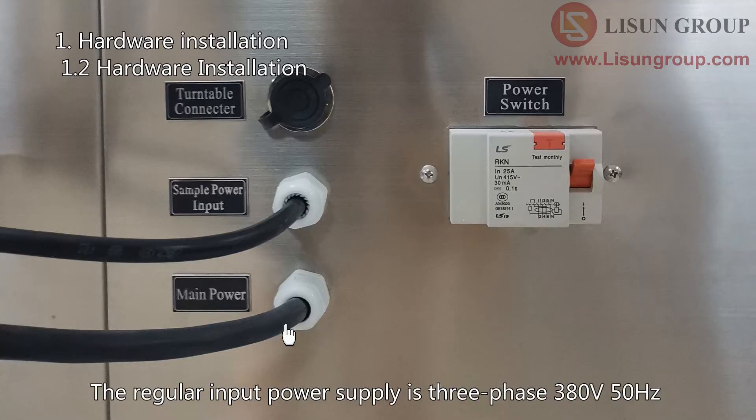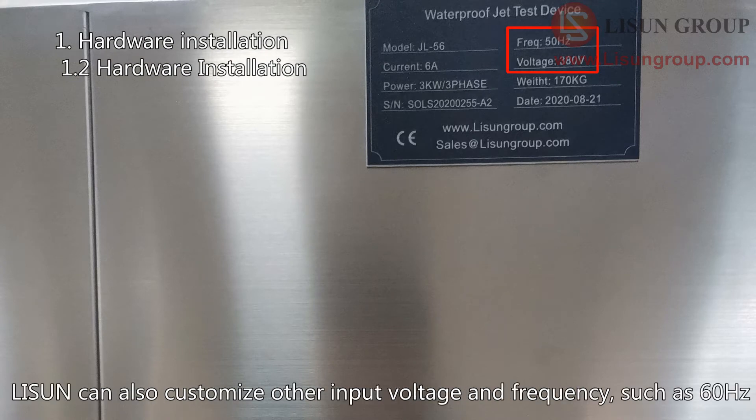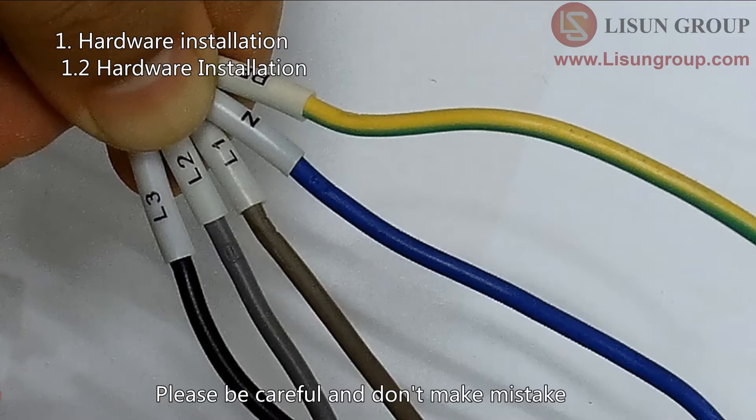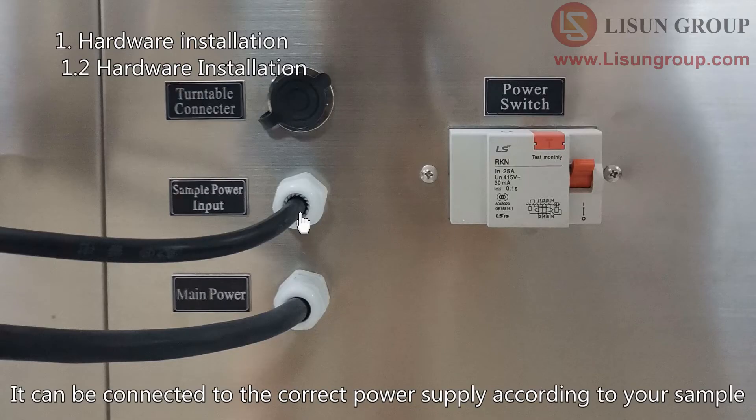This is the power cord of the device. The regular input power supply is 3-phase 380 volts, 50 hertz. Lisun can also customize other input voltage and frequency, such as 60 hertz. The phase sequence is marked on the wires — please be careful and don't make a mistake. This is the sample power cord; it can be connected to the correct power supply according to your sample.